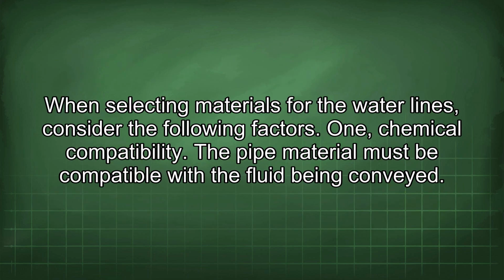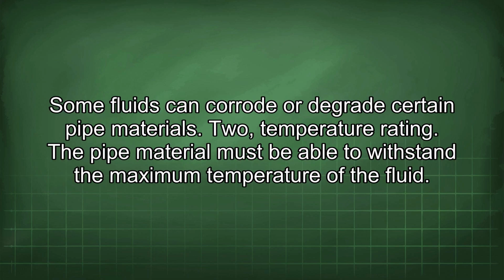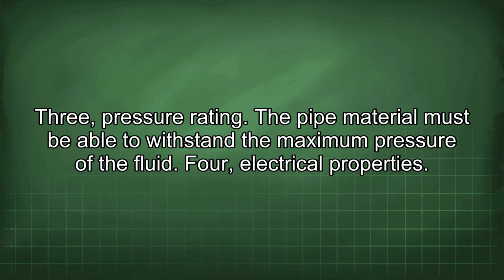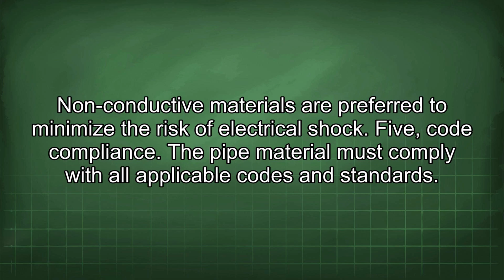When selecting materials for the water lines, consider the following factors. 1. Chemical compatibility. The pipe material must be compatible with the fluid being conveyed. Some fluids can corrode or degrade certain pipe materials. 2. Temperature rating. The pipe material must be able to withstand the maximum temperature of the fluid. 3. Pressure rating. The pipe material must be able to withstand the maximum pressure of the fluid. 4. Electrical properties. Non-conductive materials are preferred to minimize the risk of electrical shock. 5. Code compliance. The pipe material must comply with all applicable codes and standards.